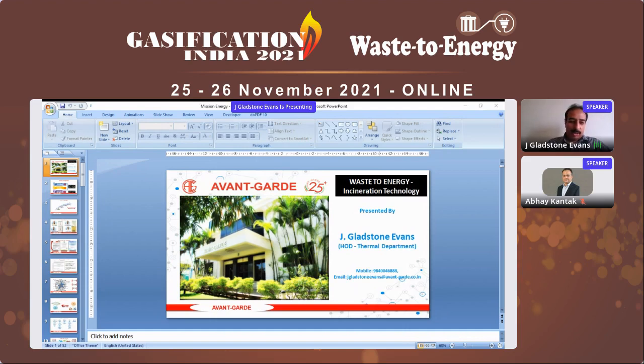And this is the project which we commissioned in Hyderabad 1 year ago. This is also generating around 27 megawatt of power, because the calorific value of Hyderabad waste is slightly better when compared to Delhi. In this plant, we have achieved almost 10% auxiliary power consumption, because our initial prediction was around 15%. We are able to achieve 10% by using the latest technologies and providing VFDs for most of the equipment. So this is the operating screenshot of this plant.